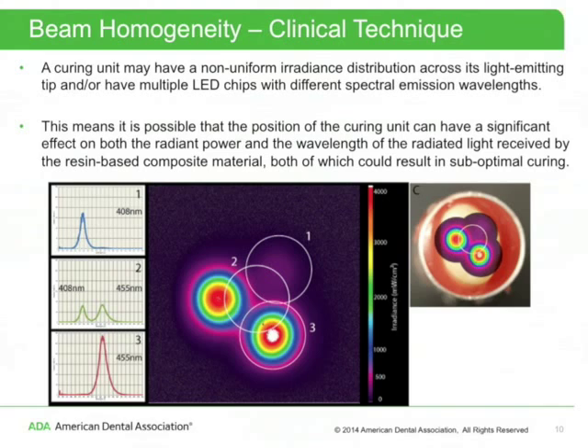This means the position of the curing unit can have a significant effect on both the radiant power and the wavelength of the radiated light received by the resin-based composite, both of which could result in sub-optimal curing. For example, if placing a Class I restorative with a diameter of about 4 mm using a material with camphorquinone as the photo initiator, it's possible the curing unit can be positioned such that circle 1 corresponds with the restoration area, meaning the energy deposited will not be at the proper wavelength to optimally interact with camphorquinone, resulting in sub-optimal curing.